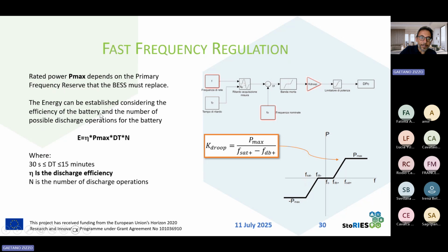Then, for calculating the energy that must be stored into the storage system, we can multiply Pmax by the discharging efficiency of the batteries, and by the number of times in which the service must be delivered, so the number of discharge operations imposed to that system, and then we can impose the discharge time that, depending on the local regulation, can be between 30 seconds and 15 minutes. Since we are sizing the system only for participating in primary frequency regulation.